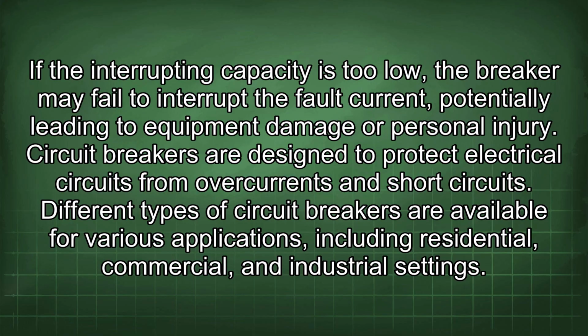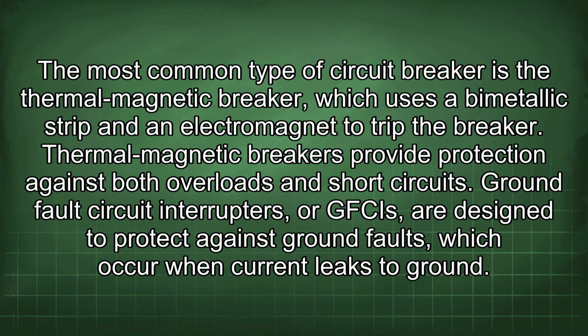Different types of circuit breakers are available for various applications, including residential, commercial, and industrial settings. The most common type of circuit breaker is the thermal magnetic breaker, which uses a bimetallic strip and an electromagnet to trip the breaker. Thermal magnetic breakers provide protection against both overloads and short circuits.